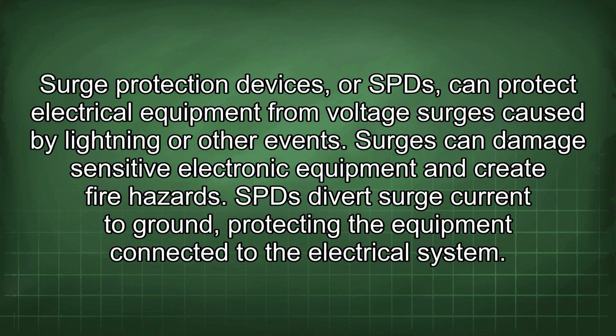Surge protection devices, or SPDs, can protect electrical equipment from voltage surges caused by lightning or other events. Surges can damage sensitive electronic equipment and create fire hazards. An SPD diverts surge current to ground, protecting the equipment connected to the electrical system.